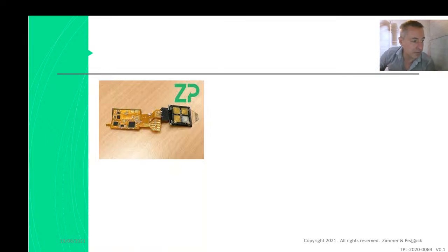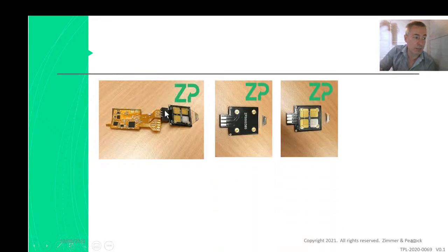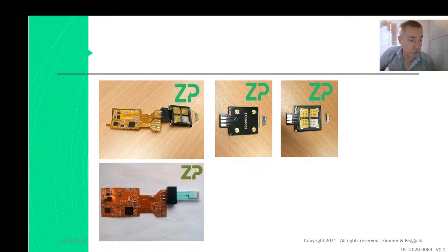So this is the EasyFlex with the microneedles plugged into it. There's a connector here, so you can literally just unplug the microneedles. They plug in and out. So essentially you get the board and then you just plug the microneedles in. You can also just put other glucose electrodes in there as well. There are some videos of us doing this kind of testing with EasyFlex, but it's fairly straightforward to do. You get this board, you make a Bluetooth connection with it. The Bluetooth aerial is actually this little dot here.